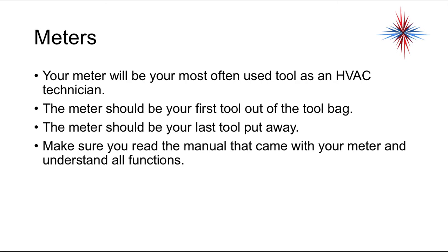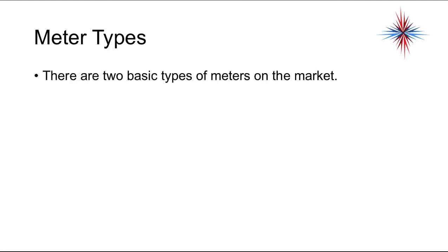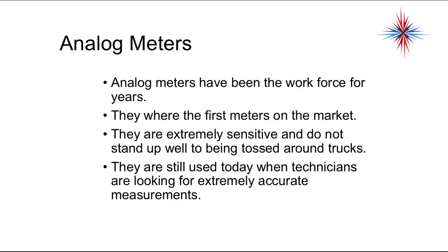Now, the reason that we want it to be the first tool out is in order to safely work on equipment, you have to know whether or not you have voltage. It should also be the last tool you put away because you should be checking all your work once you're complete. Most meters also have some temperature gauges on it, temp sensors, so you're going to use it all the way through. There are two basic types of meters on the market.